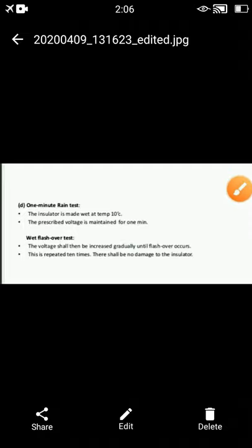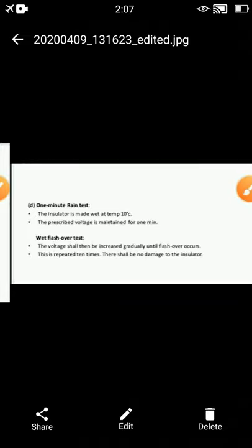The next type is the one minute rain test. In this test, the insulator is made wet at a temperature of 10 degrees Celsius, and the prescribed voltage is maintained for one minute. The last type test is the wet flashover test, in which the voltage is increased gradually until flashover occurs. This is repeated ten times and there shall be no damage to the insulator. These are the different sub-types under the type test.